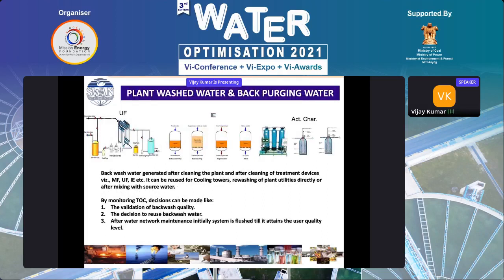Of course, many people who work on water chemistry in a power plant know all these things, but still I want to say a little about them here. Membrane filtration, ultrafiltration, and ion exchange towers all require some regeneration or backwash to make sure accumulation of organics does not happen over a long time, which deteriorates product quality. So when to stop the backwash, and how much backwash is required, TOC is a good indicator for that, since you are using good water for it. All this regeneration and backwash water again goes through a neutralization pit and can be reused. So this is how you take decisions by monitoring TOC.